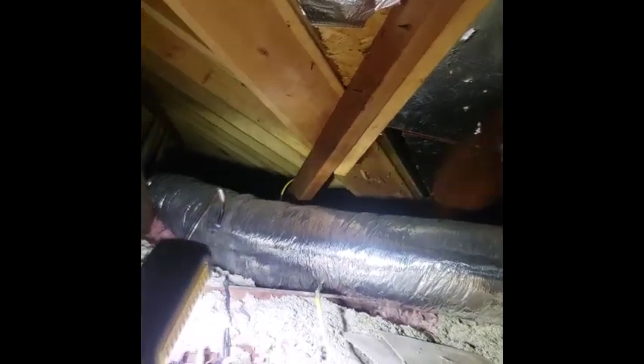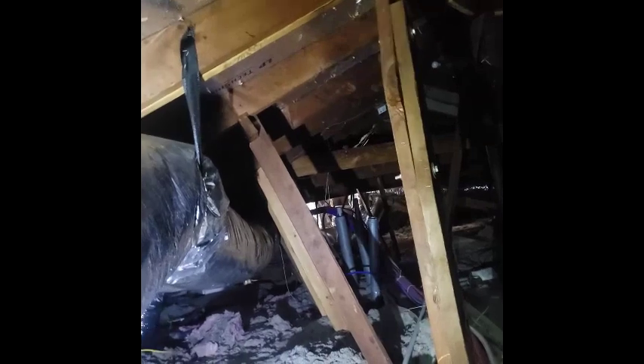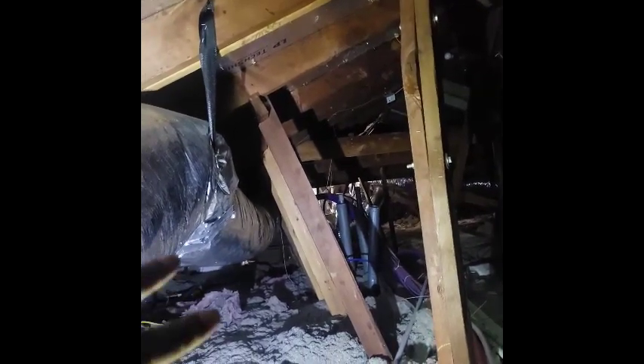maximum. So I'm thinking about either just building a box right here off this 10 or 12 inch duct, shorten and build a box in the middle, and then run my duct work. Maybe that'll help get more airflow. Either that, but that's a spider web up there. I'm gonna need to start from scratch. I don't really know what they got going on. But either that or install some dampers. Because the living room area, where they say they don't use much, they get very cold here, and it's a dining room area that's blowing a lot of CFM. I can install some dampers and maybe shut them down to about 80 or 90%. And it'll push more air down this way.